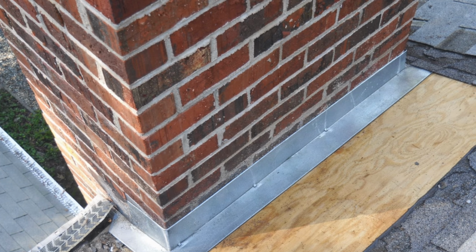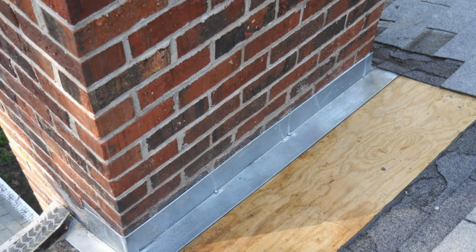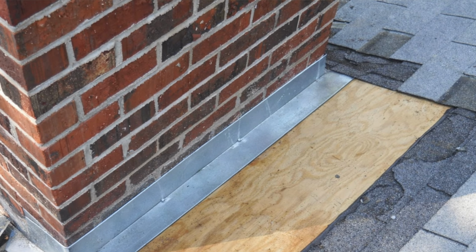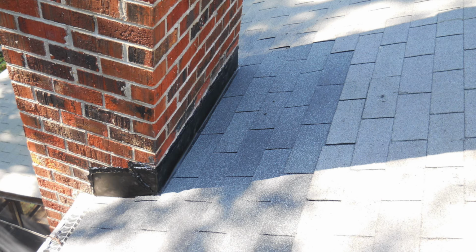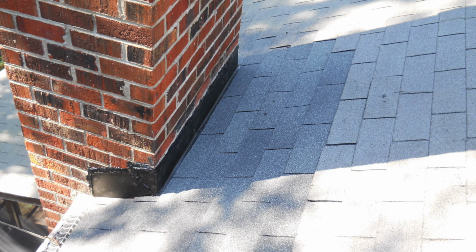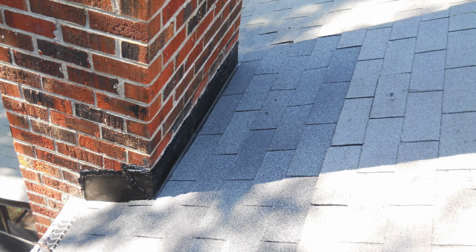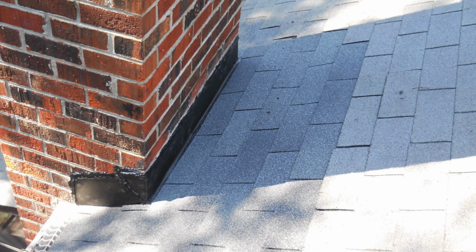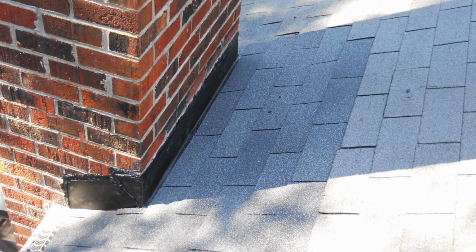A common and acceptable method to bridge this gap structurally is to fasten strips of sheet metal over the opening. These metal strips cover the clearance space and extend onto the roof sheathing by an additional 4 inches. They can be secured with construction adhesives such as liquid nails. Once the roofing underlayment, step flashing, and counter flashing are installed over top, this assembly reinforces the metal-covered gap and restores structural stability while maintaining the required non-combustible clearance.